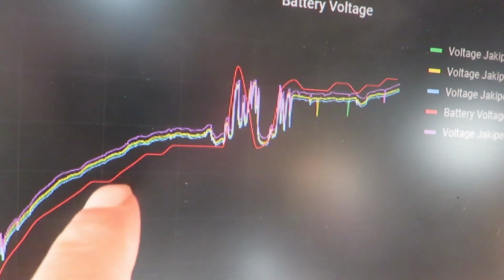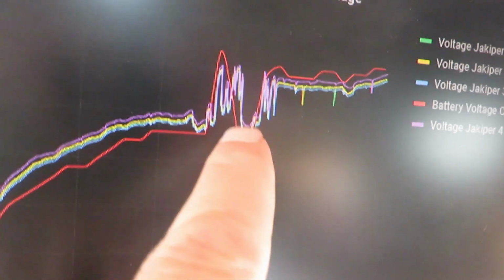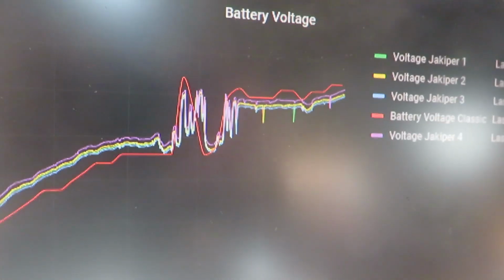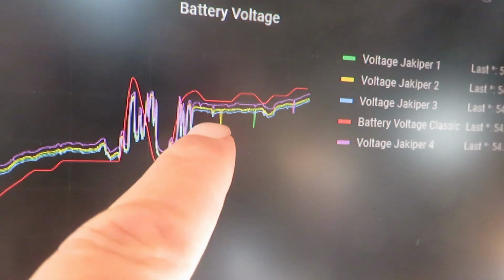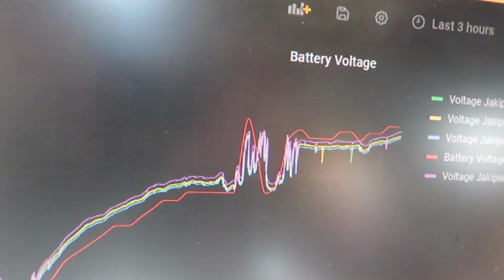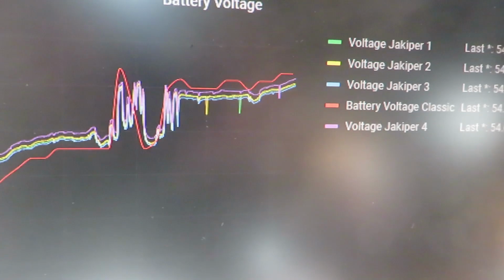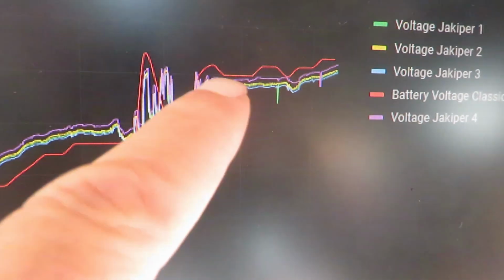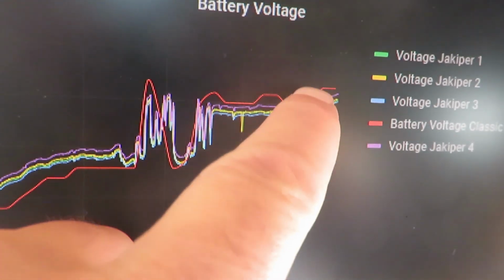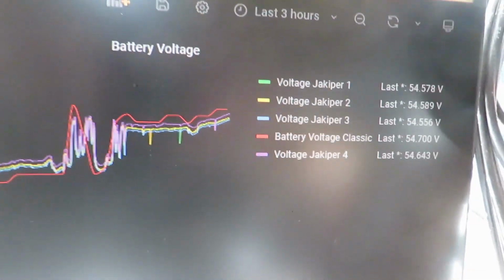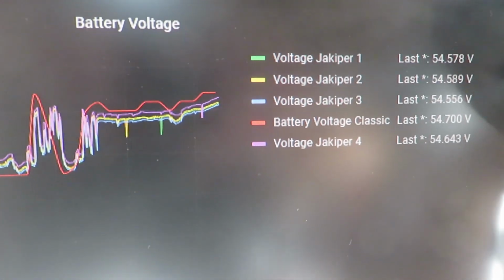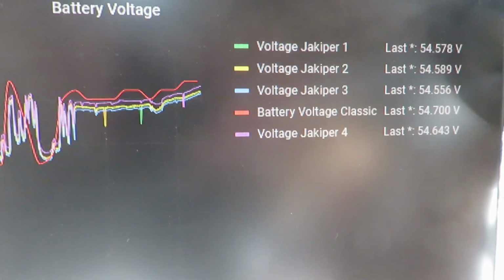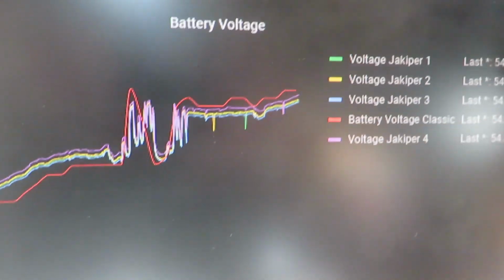So here's the voltage. I have to play around with it. This is what my Classic charge controller has, and I have to compensate because it doesn't have voltage sense. As the power goes up on it, that's the red line. As the power goes up on the batteries, it'll eventually match more what the controller's seeing. So that's just one thing I have to do because I have an old charge controller, to kind of trick it into being the right spot at the top.